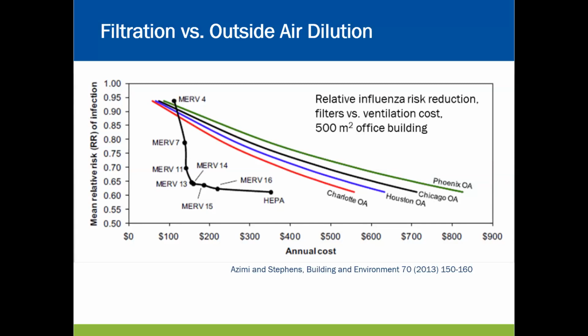Once you get to a MERV 13, you're doing pretty good. The other colored lines show increasing ventilation, which costs a bit more than adding filtration, but there are other benefits to that as well. You can see how adding additional outside air really drops the risk of infection. So we like to make sure a place has at least a minimum amount of outside air, try to grow that some, and also improve the filtration as much as possible. You have to look at each scenario to see the best trade-off.